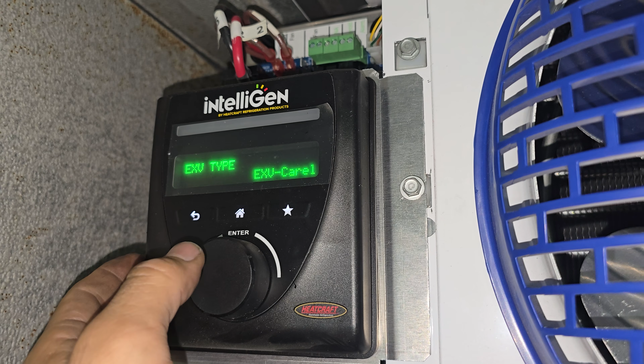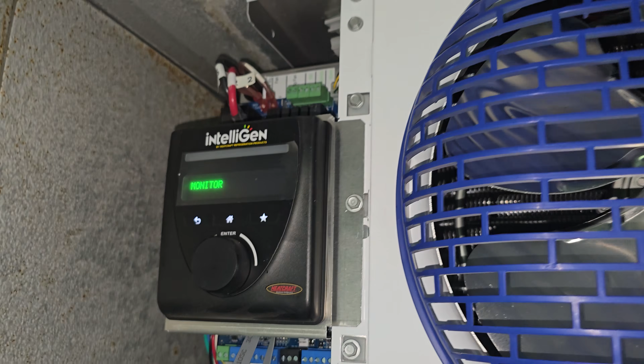Box temp set point - we need to get that from the manager, but I think it's 27 that they want. Start system. So we got to wait a minute, it's in a delay, and then it'll open up the EEV, and they're starting to get ready to charge it on the roof.